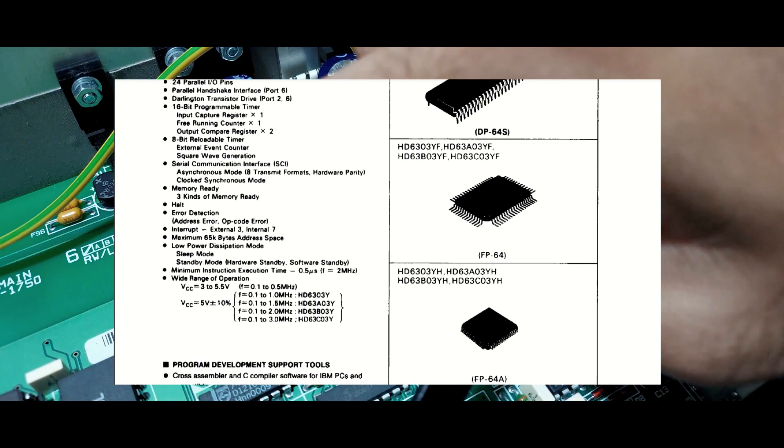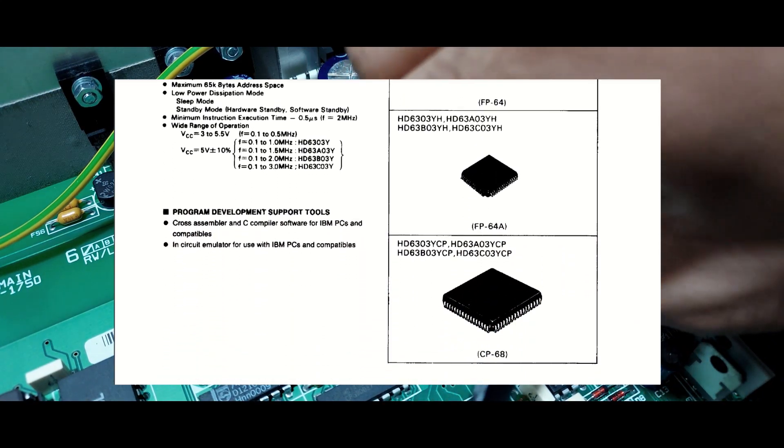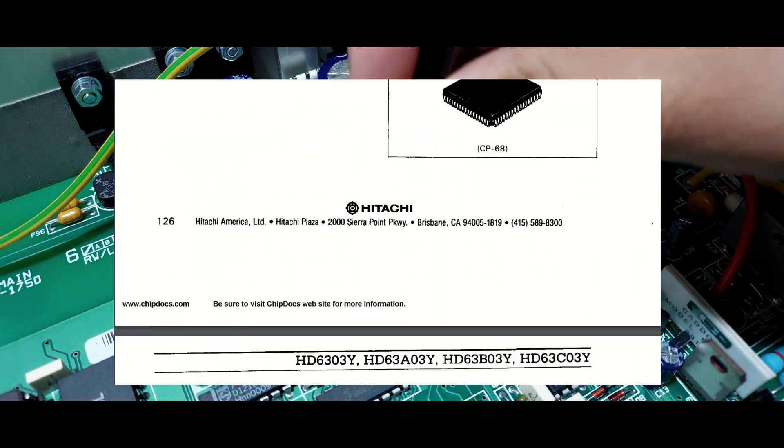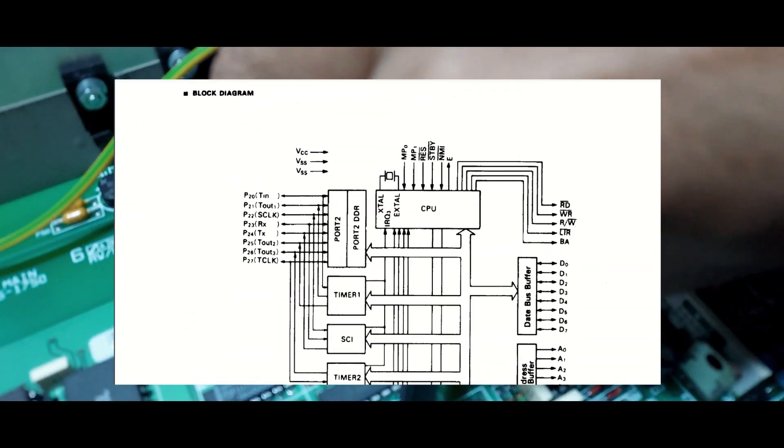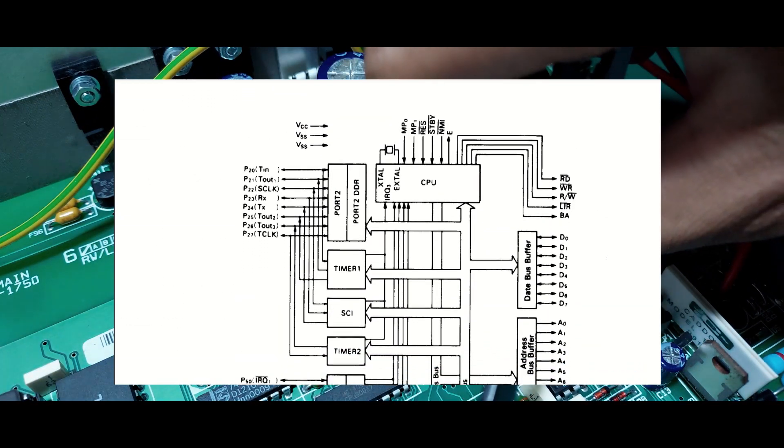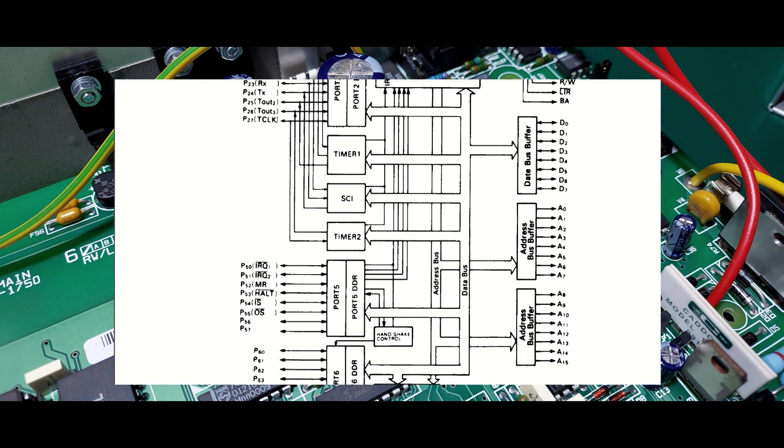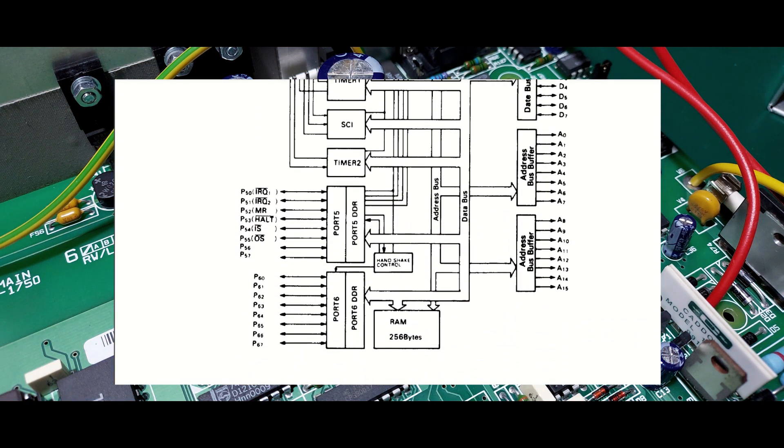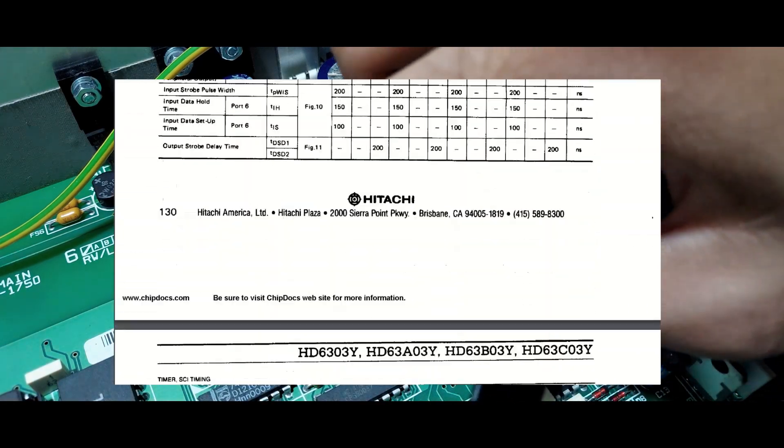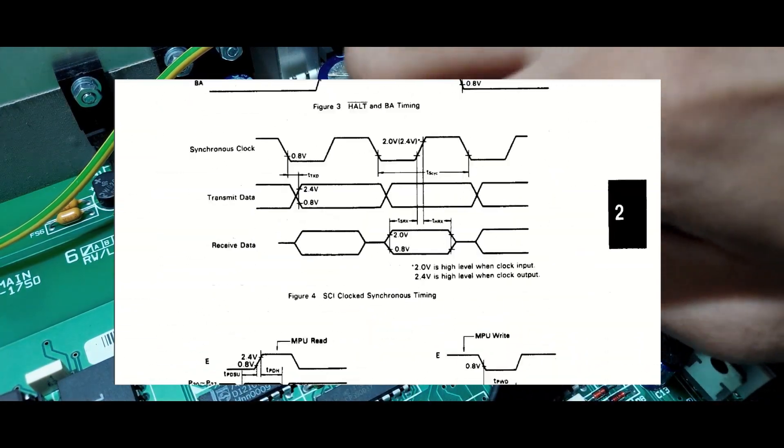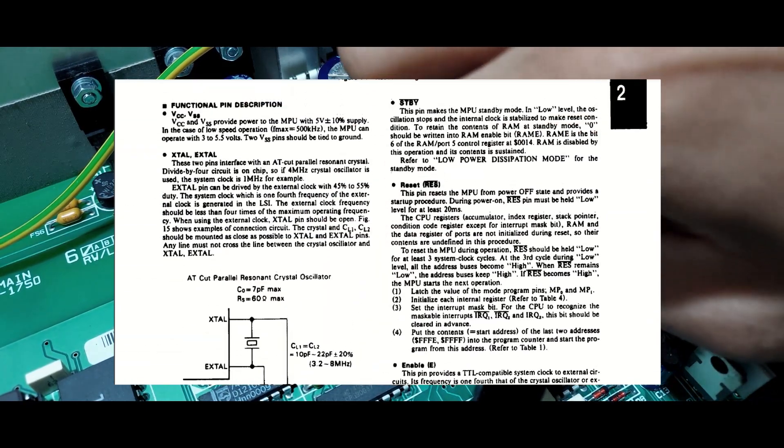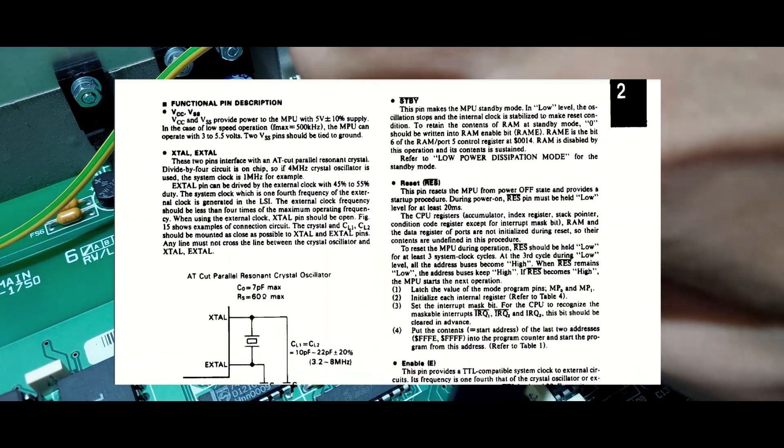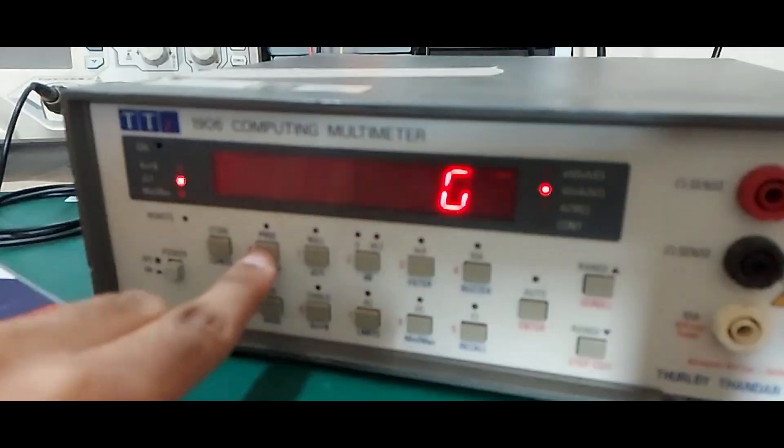The MPU handles a variety of tasks such as multiplexing the keypad or keyboard matrix and reading the key inputs, as well as multiplexing and driving the front panel display, handling RS-232 and GPIB communication, as well as playing a critical role in the computing of signals by reading from the analog to digital converter and feeding back to the ADC and measurement control section to configure the signal paths by toggling many CMOS gates and MOSFETs.